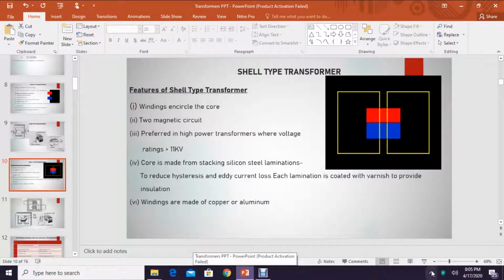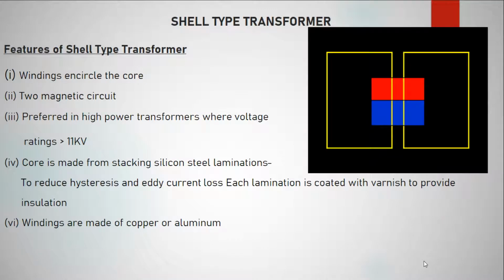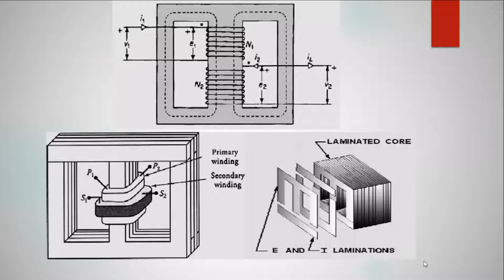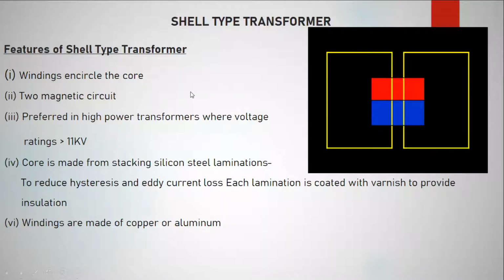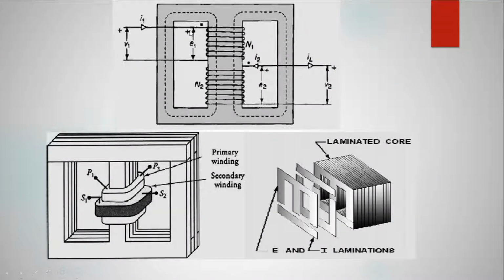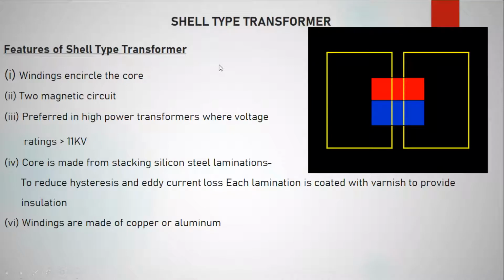Shell type transformers. This is shell type transformers. Features of the shell type transformers: windings encircle the core. These are the windings which encircle the core. Unlike a core type transformer, here two magnetic circuits are provided because of its construction, as the windings encircle the core. Two magnetic circuits will be there.